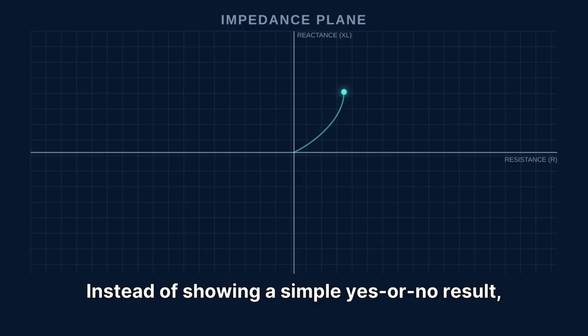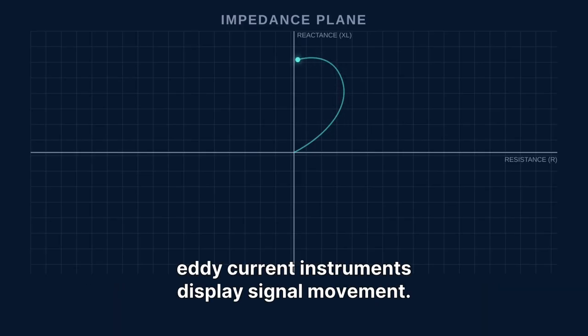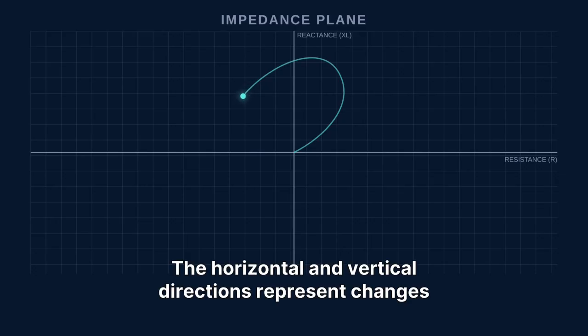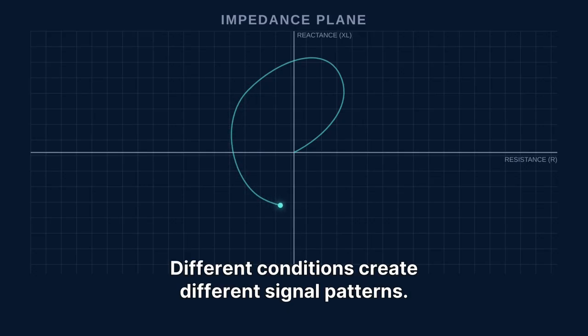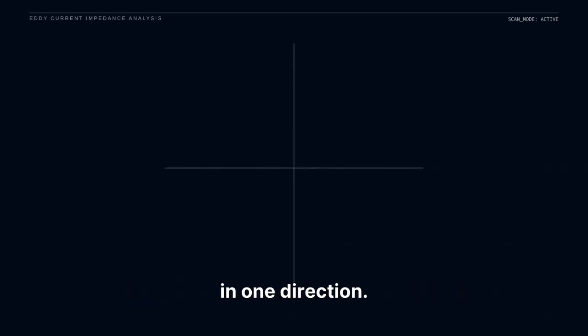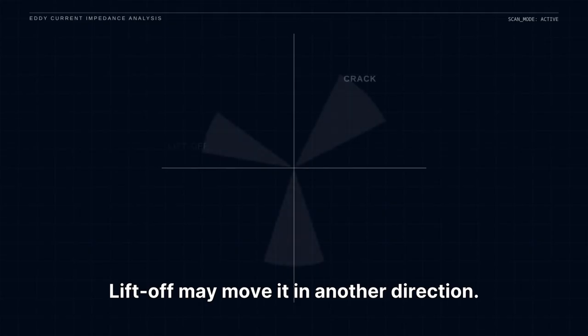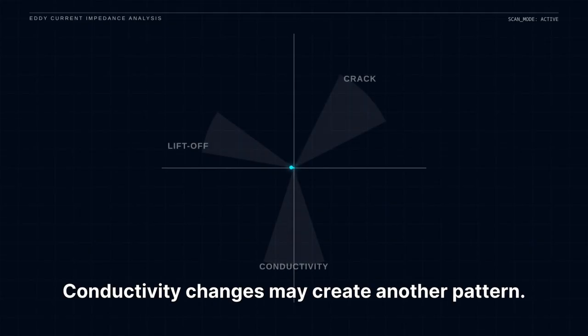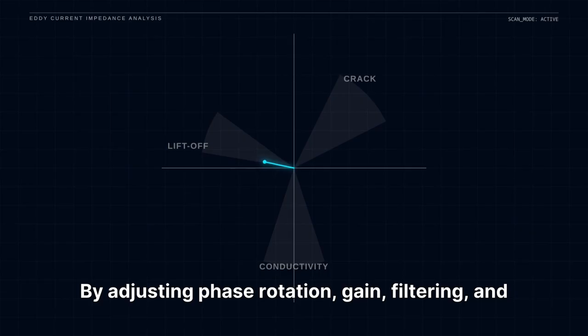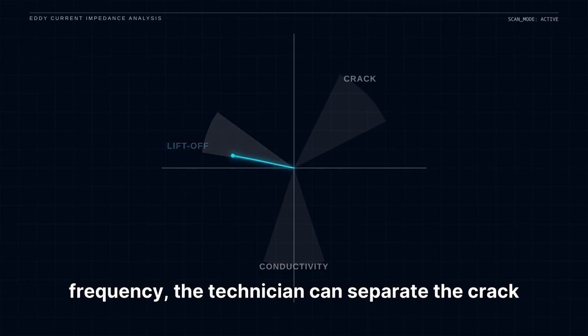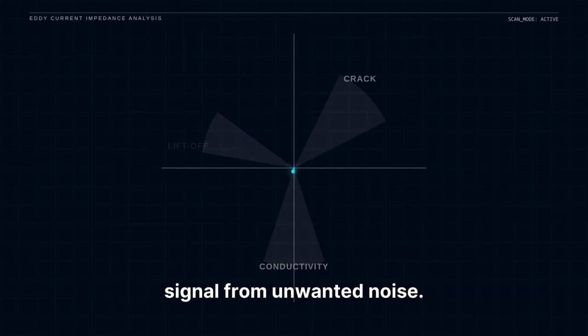The heart of eddy current interpretation is the impedance plane. Instead of showing a simple yes or no result, eddy current instruments display signal movement. The horizontal and vertical directions represent changes in coil impedance. Different conditions create different signal patterns. A surface crack may move the signal in one direction. Liftoff may move it in another direction. Conductivity changes may create another pattern. By adjusting phase rotation, gain, filtering, and frequency, the technician can separate the crack signal from unwanted noise.